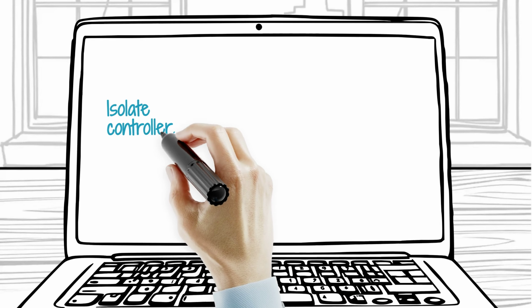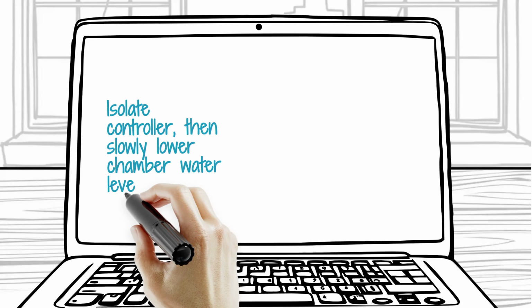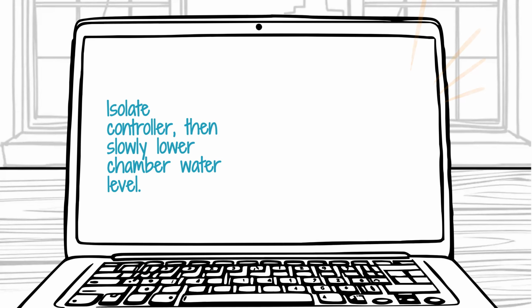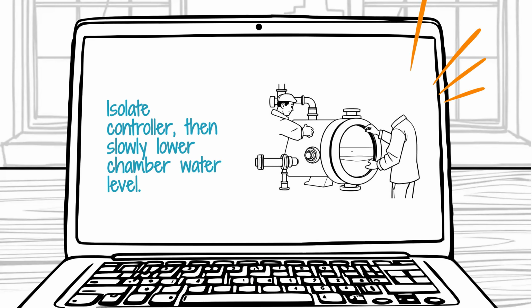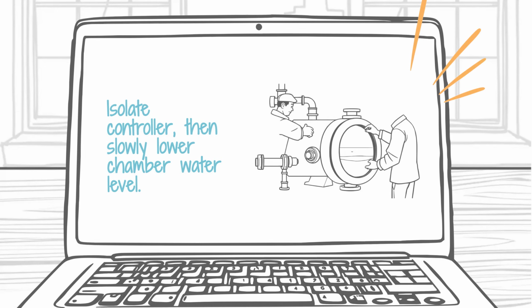To begin the physical test, you must isolate the level controller from the boiler by closing the steam and water balance valves. Carefully open the drain valve on the float chamber to slowly lower the water level inside the housing while the actual boiler water level remains safe.